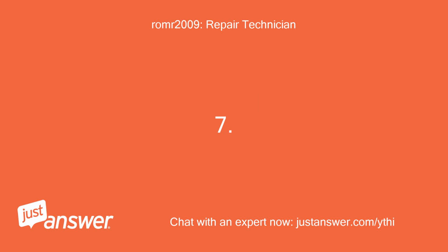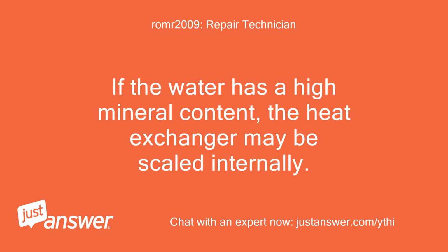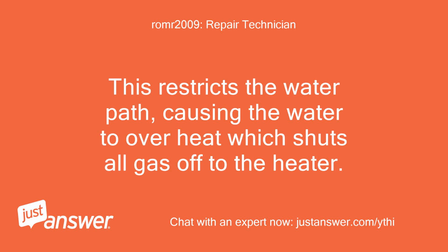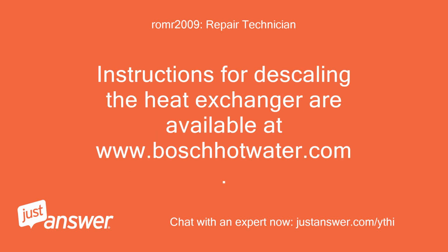7. If the water has a high mineral content, the heat exchanger may be scaled internally. This restricts the water path, causing the water to overheat, which shuts all gas off to the heater. Instructions for descaling the heat exchanger are available at www.boschhotwater.com.